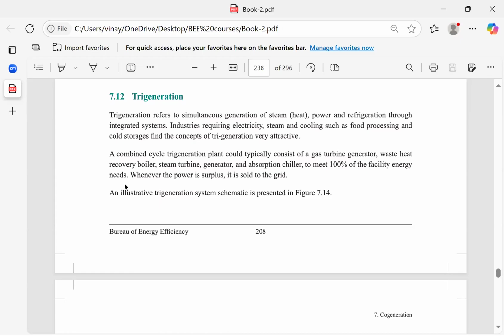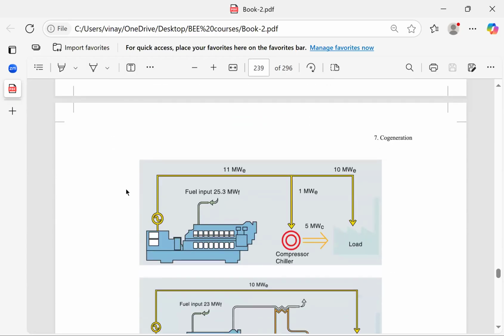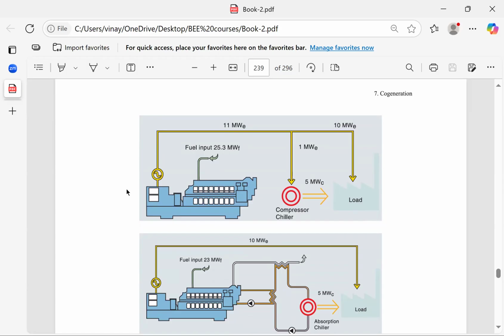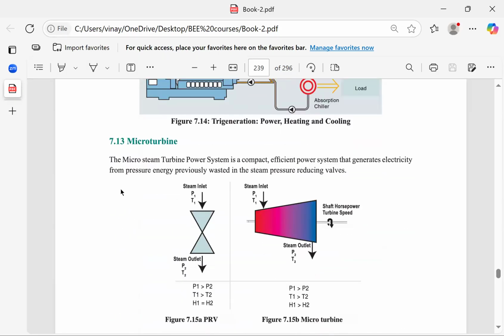For example, there is a cold house where refrigeration products are stored in a hall. Their requirement is also for refrigeration, so they need heat to operate absorption type chillers. They will have only one single gas turbine using natural gas. The exhaust gases heat a steam boiler, that steam operates a steam turbine, and the steam turbine exhaust or extractions can be used for process or for refrigeration. This is tri-generation. You can find many tri-generation sectors, in the medical industry, dairy industry, or even fertilizer industry. These are just the uses of the same heat in different streams.